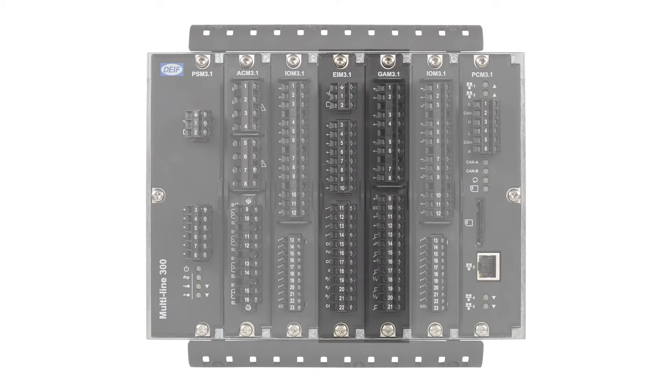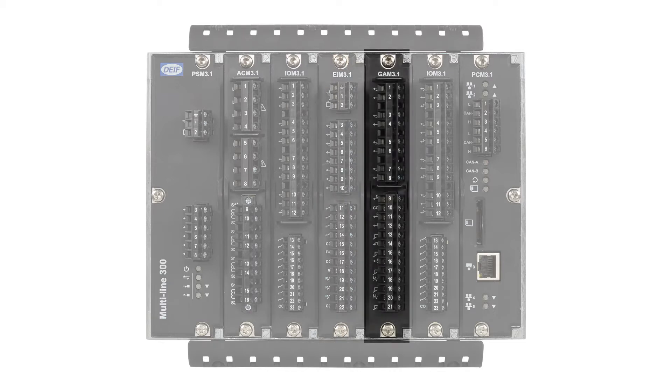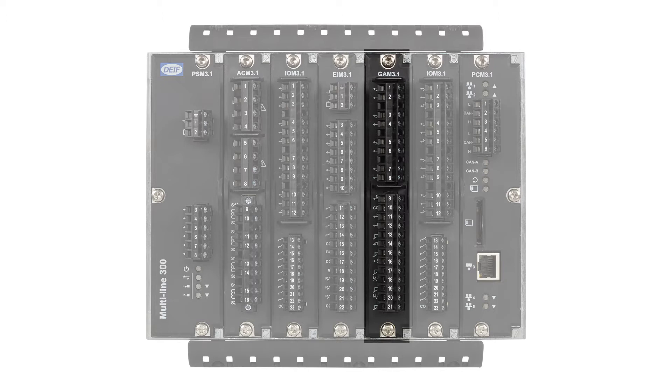The governor and automatic voltage regulator module GAM 3.1 is installed in the genset and emergency genset controller types. It has four relay outputs, three analog outputs, and two analog inputs. These are all configurable.